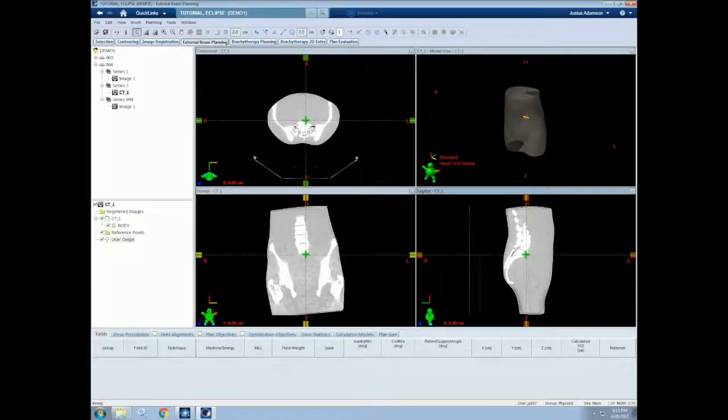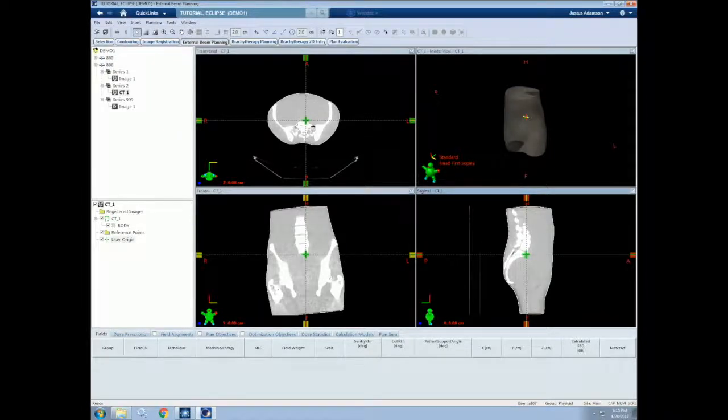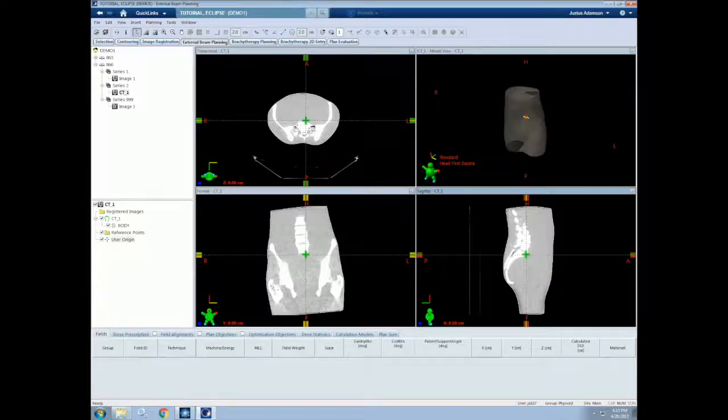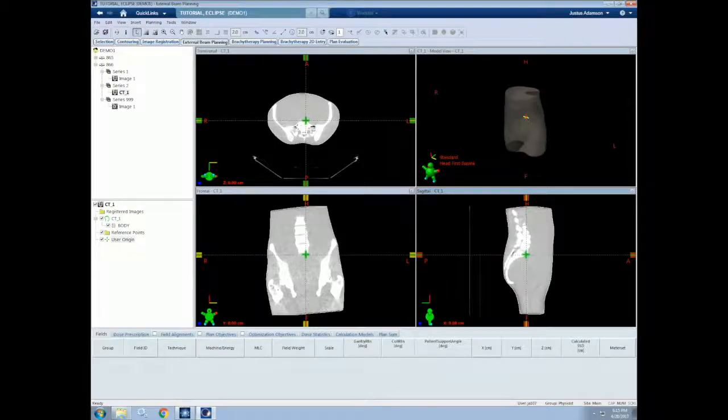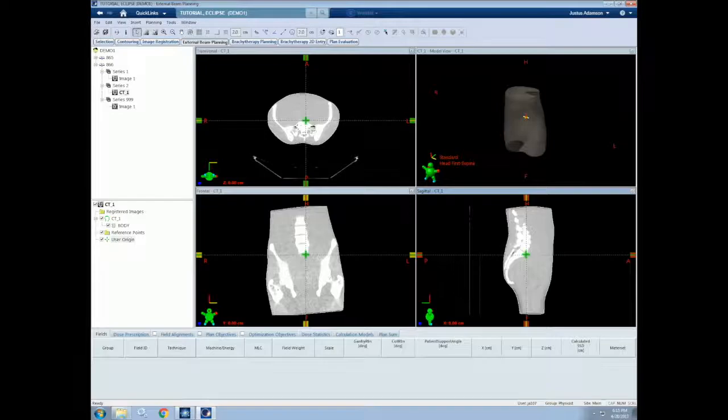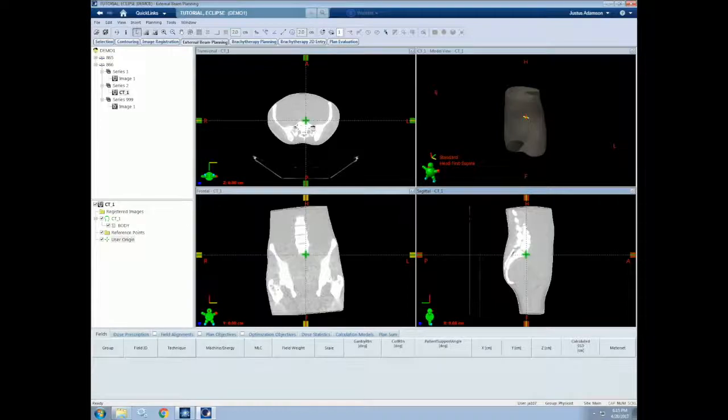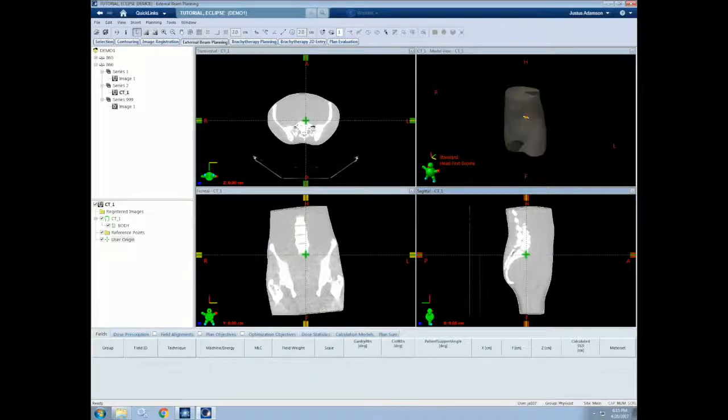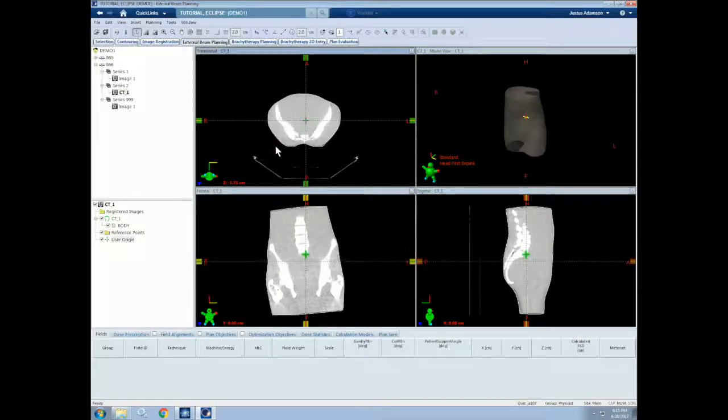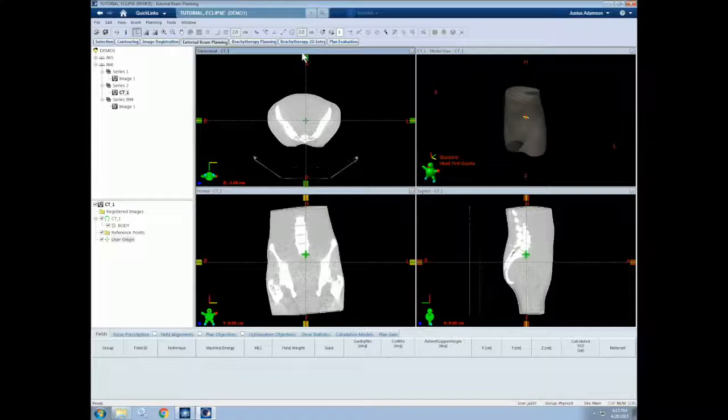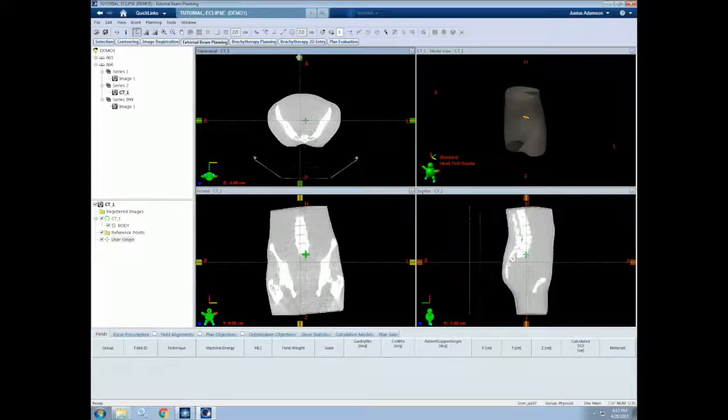Another important skill is knowing how to set the CT origin, or in other words, moving the CT origin so that it coincides with the laser origin at the time of CT simulation. This is indicated by BBs for our patients. This is sometimes performed automatically by some CT manufacturer systems and would therefore not be necessary. To change the CT origin, first move the viewing windows to the location that the CT origin should be assigned to. For our case, we'll just move to a random viewing plane since our origin is already correct.